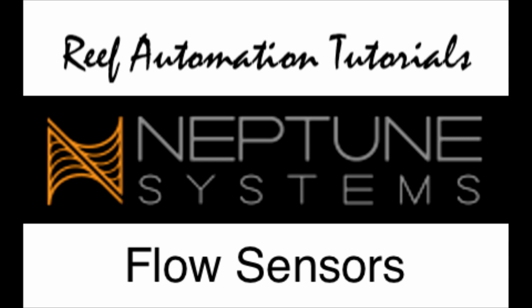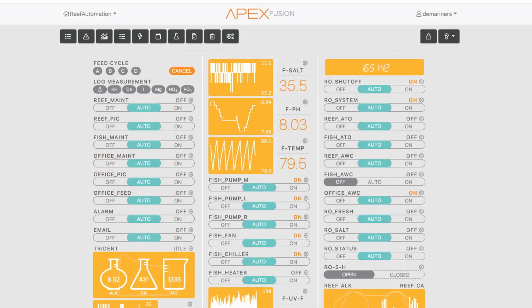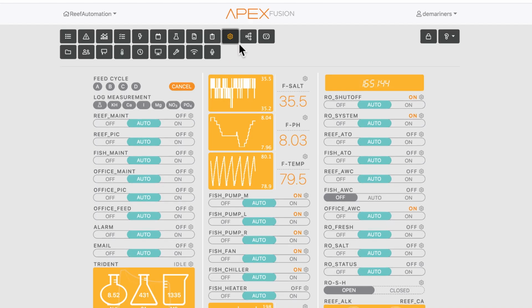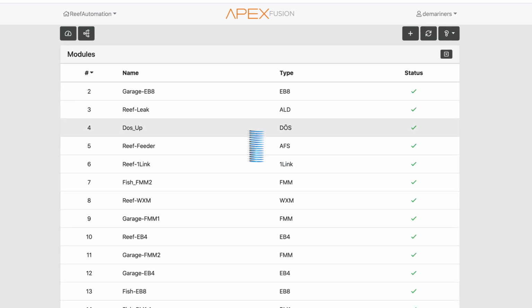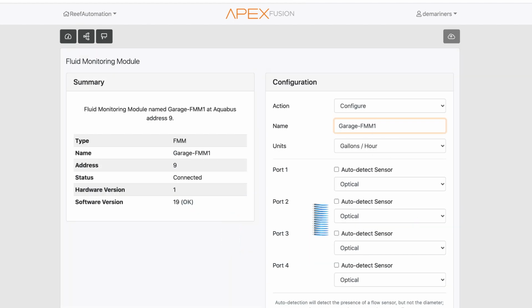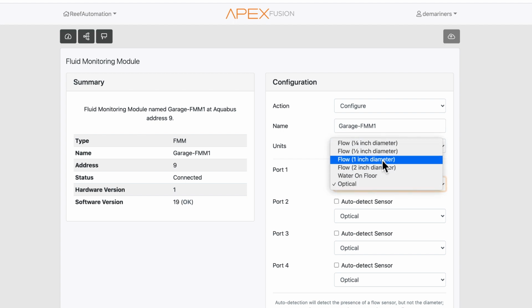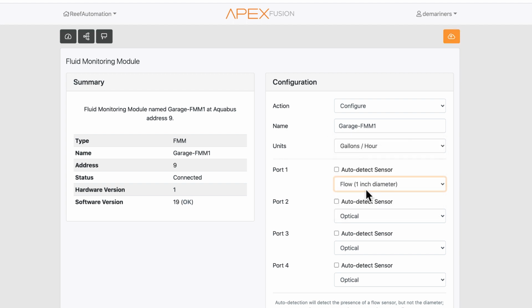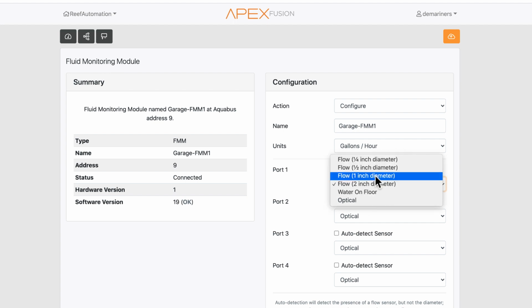So let's go through how to program them and how to get them set up. So your flow sensors are going to be located in the FMM. So if we click on the gear here, and then we click on our modules, which is this guy right here, we're going to show all of our modules that are in the system. If we go to the FMM, you will see that each port will tell you what's plugged into each port. Now, if you do auto detect, which is what I recommend most people to do, it'll automatically find which flow sensor you are using. Now, of course, you can manually put in the flow sensor as well if you'd like, right here. So I generally just put the auto detect, but if it doesn't auto detect it on the first round, I recommend just manually putting it in.